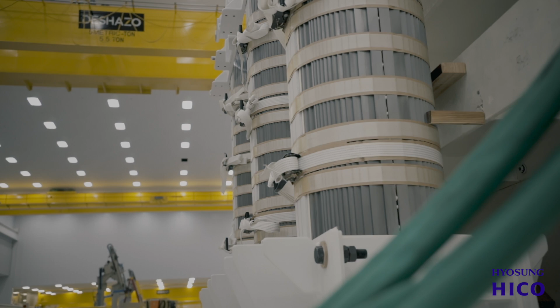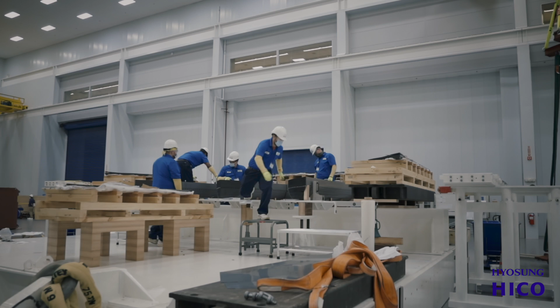My name is Ian Gowan, and I'm core stacking lead technician. In the core stacking department, we stack the core steel for inside the transformer. When we receive core steel for stacking, quantity is checked and the height of each step is checked. Quantity is the biggest deal, and it has to do with your overall height.